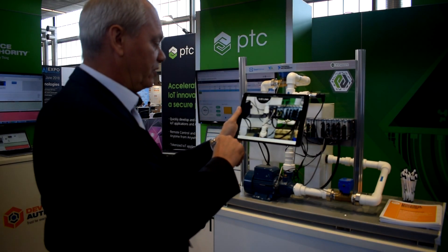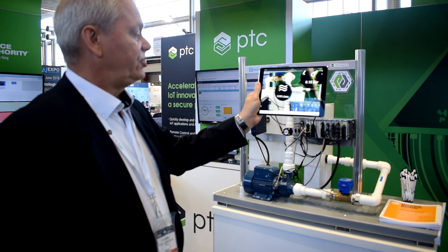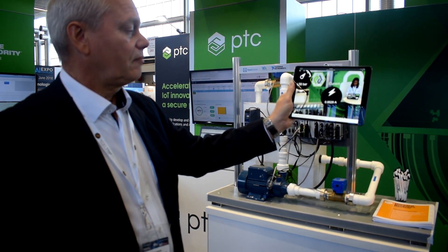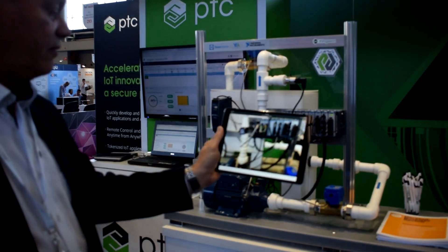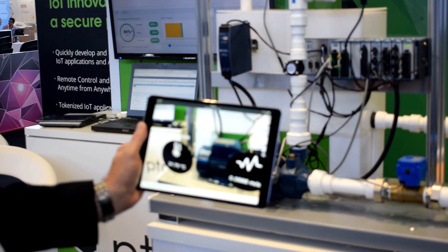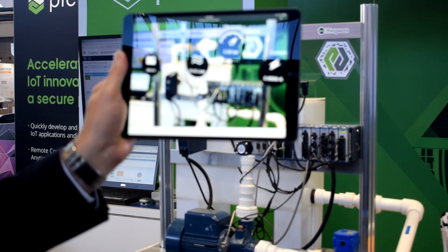Alex, could you please turn on the pump and let us show how the data changes. I can see the amps going up. I can see vibration is picking up. I can see the active temperature — there is so much going on in the right places. It looks okay. Thank you.